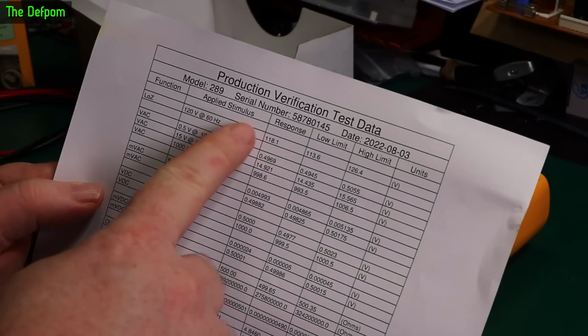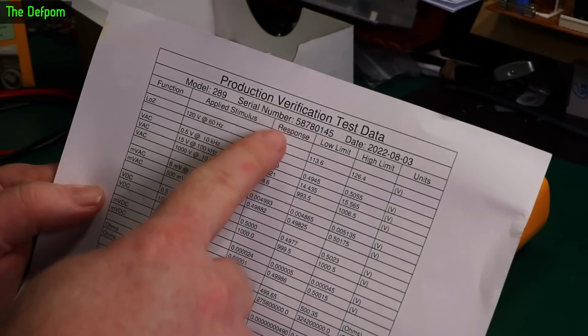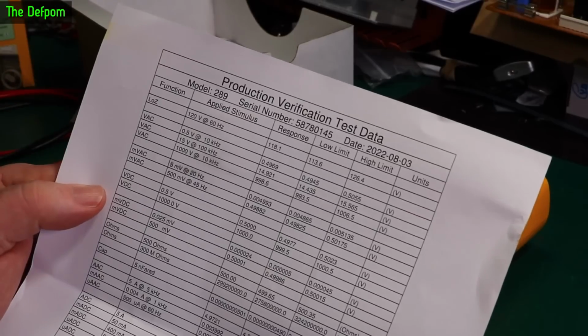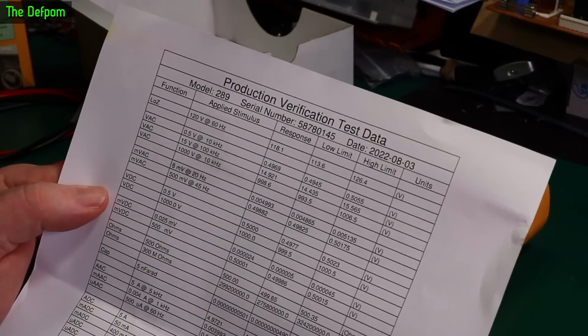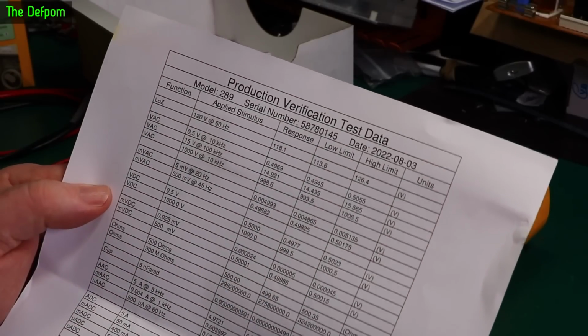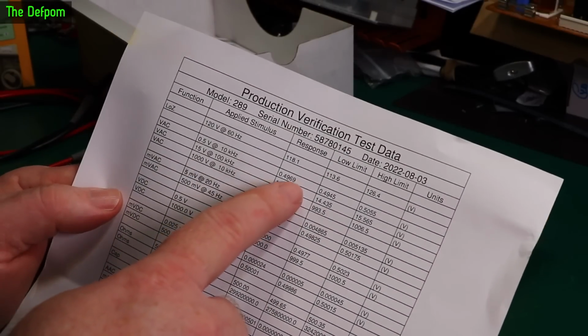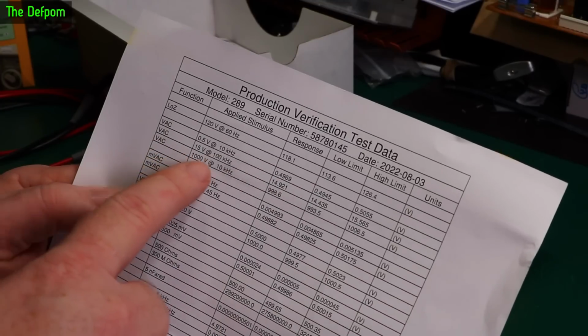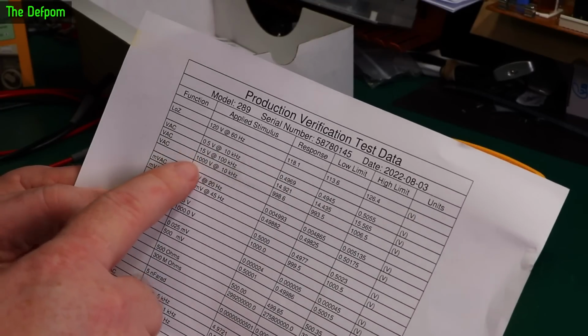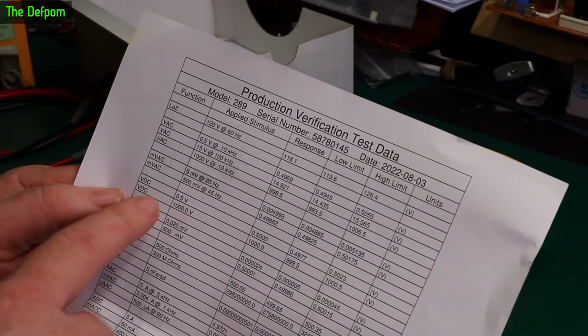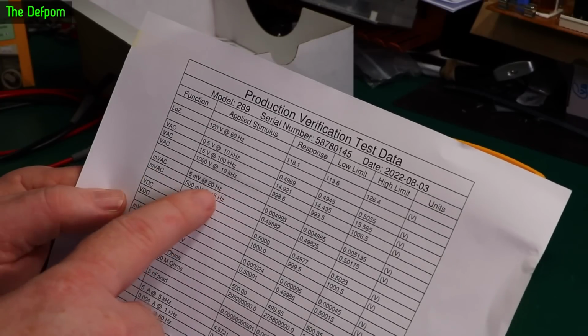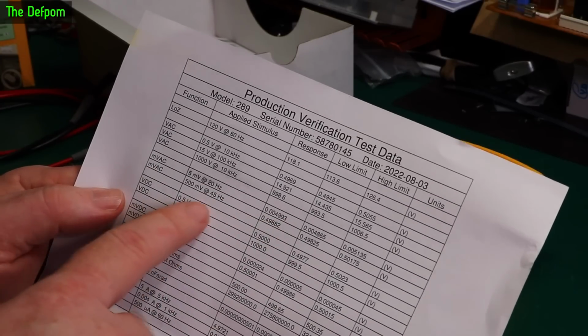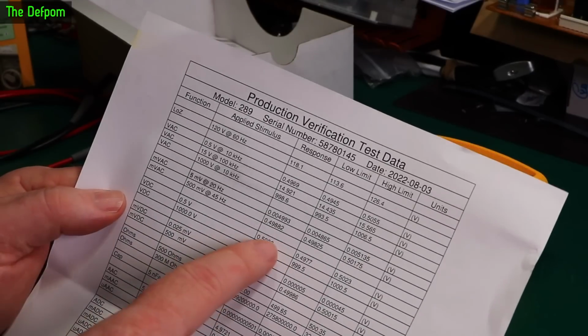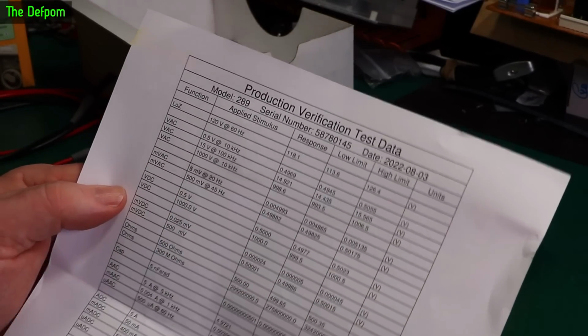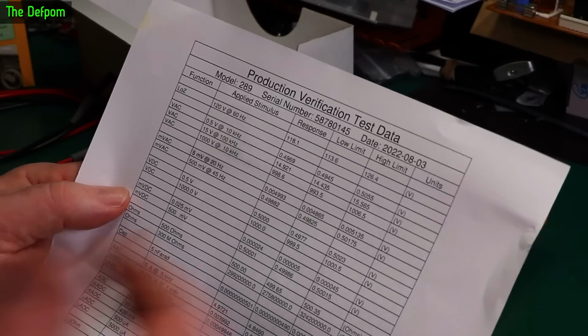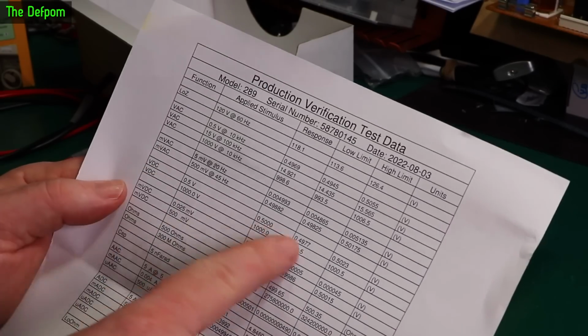Volts AC, I mean these are just a verification, right? So this is just a check. This isn't an actual calibration record. This is just a product verification, which does give you at least an indication of accuracy. You've also seen we're reading slightly down here. Yes, you were seeing that at 10 kilohertz. 100 kilohertz is the next check it did there. Millivolts AC, 20 hertz was reading down slightly. 45 hertz is reading down slightly. There's that 98 number. So yeah, that's confirming that what I'm seeing on my calibrator is basically matching what they got. So I'm pretty happy with that, and also the volts and stuff like that.